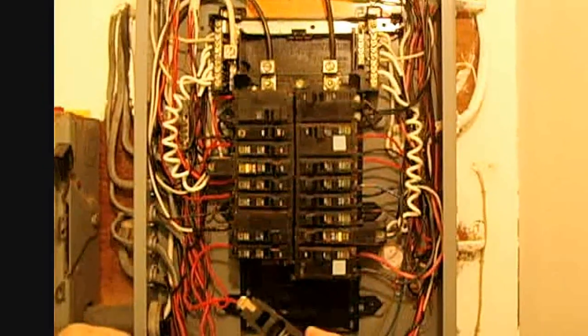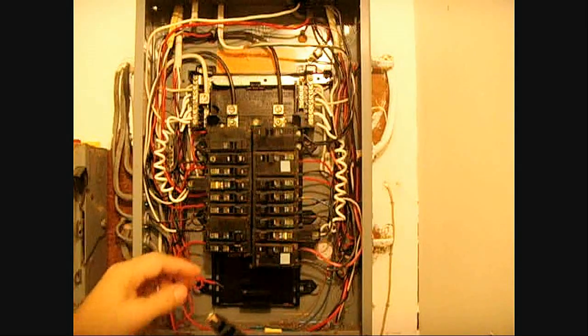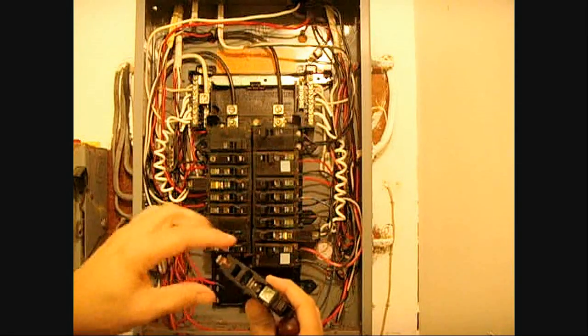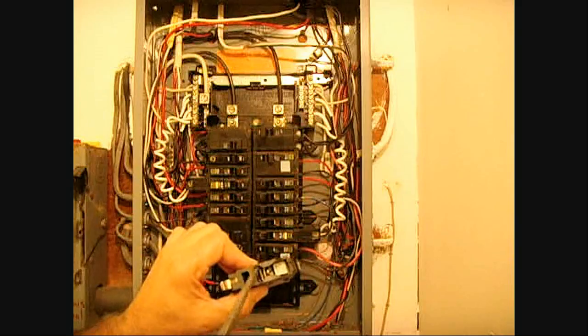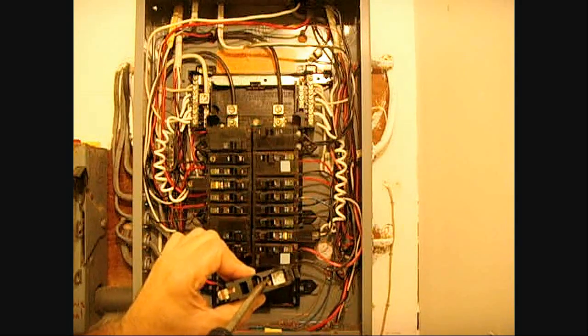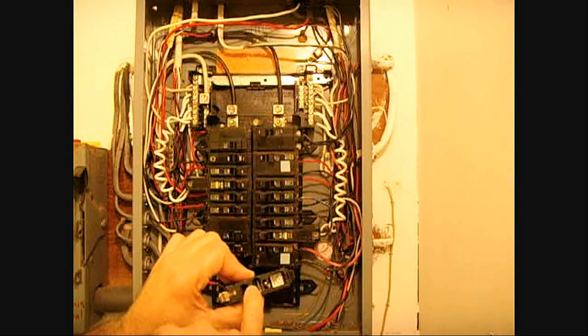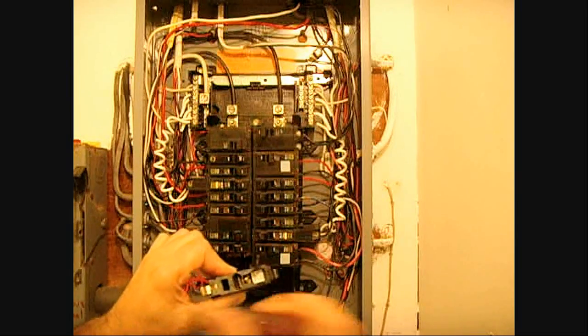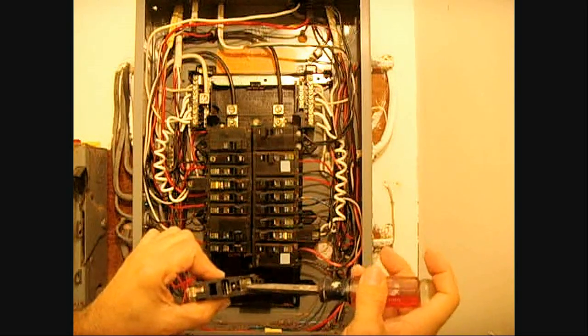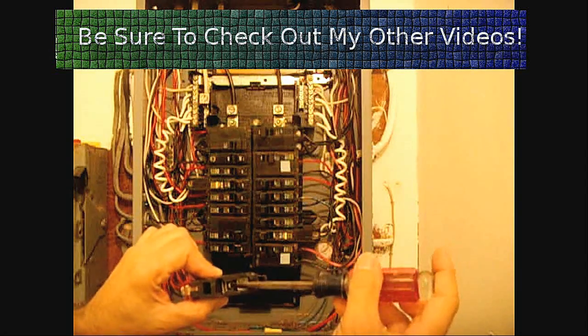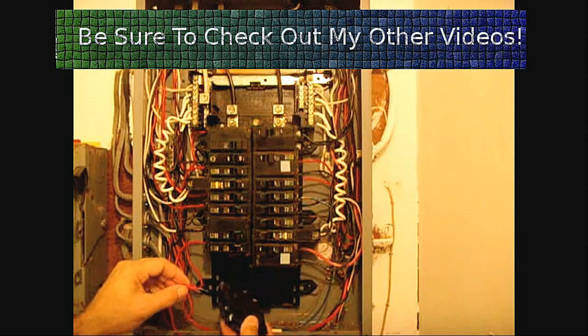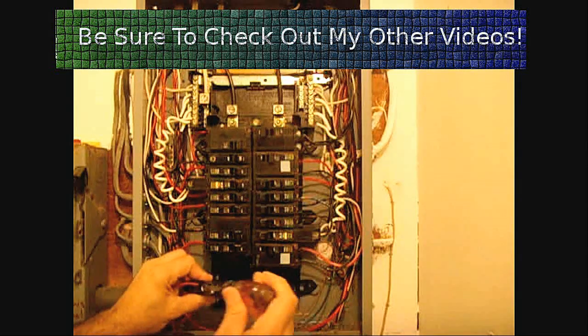So make sure when the wire is stripped, you strip off about 1/2 inch. Make sure it goes all the way in. You also have to be careful that when this is tightened down, you don't have part of the insulation in between the contacts. Because when you go to tighten this down securely, if it's not just bare copper in there, you're going to have a very bad connection, if any connection at all. So make sure you check those. Put this back. Tighten it down securely.